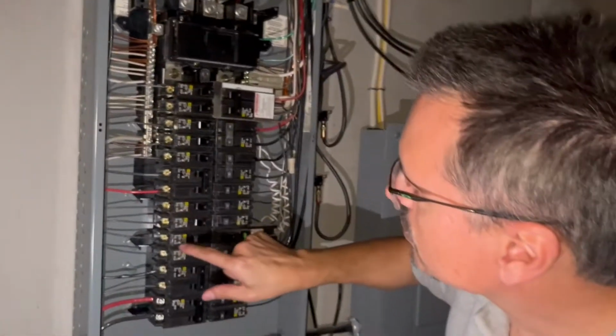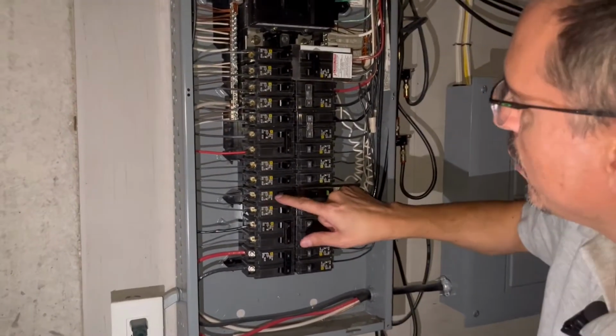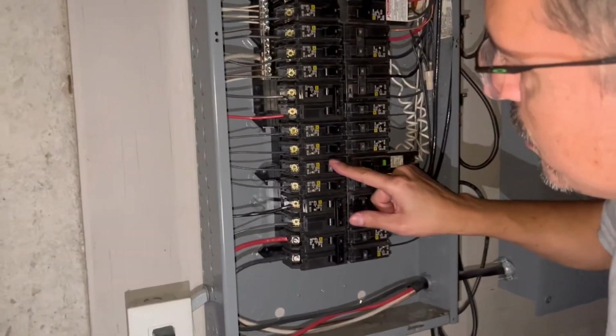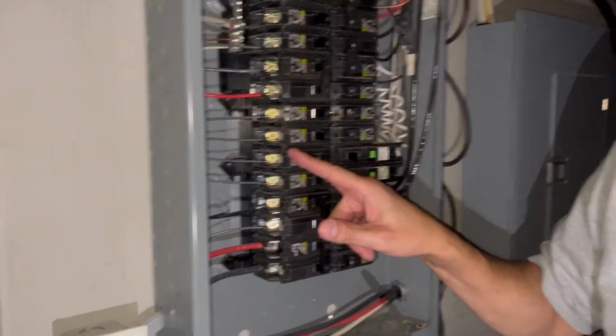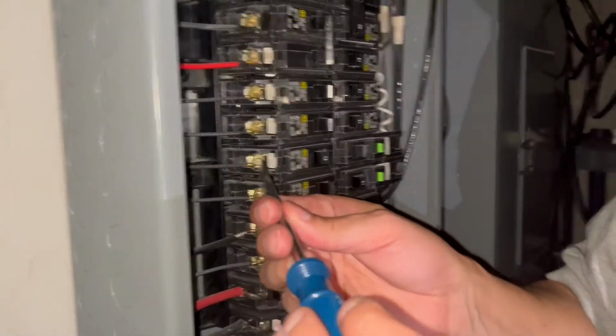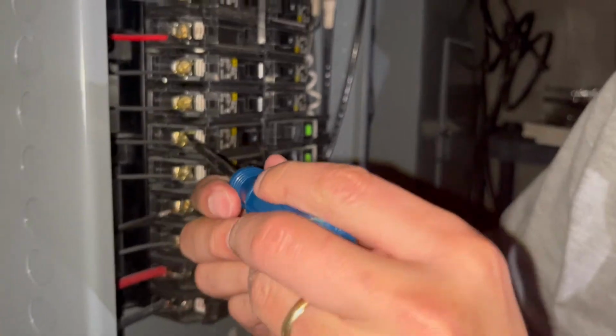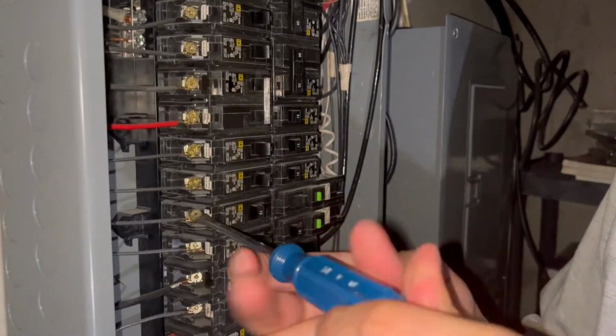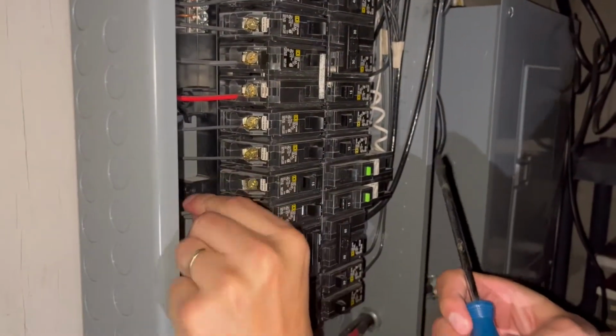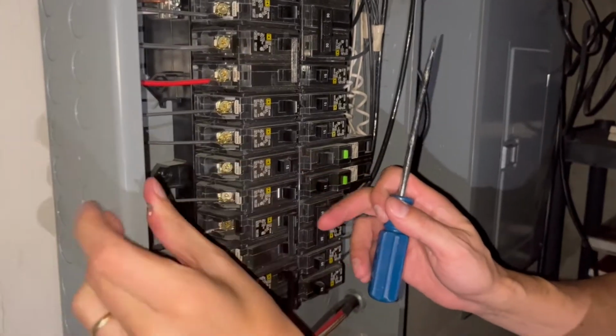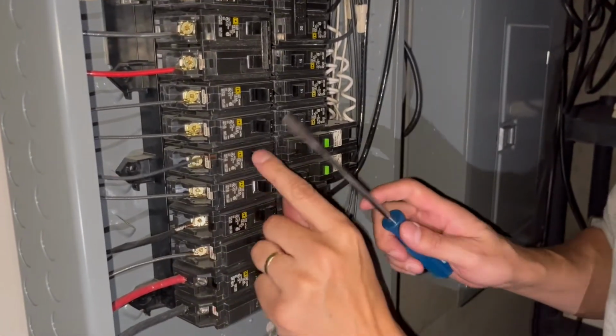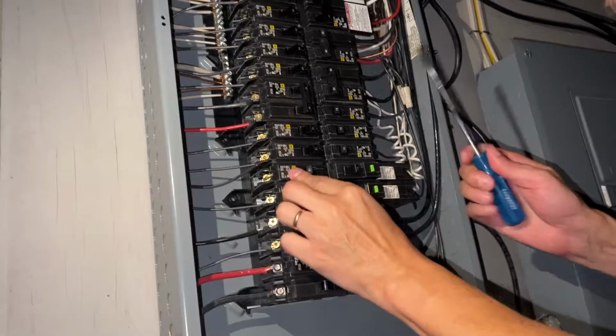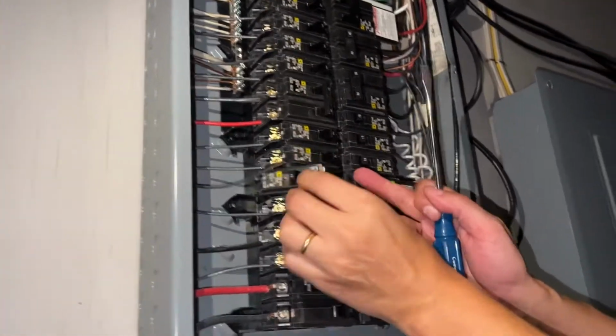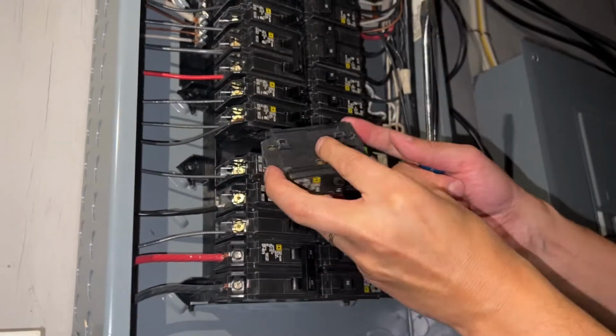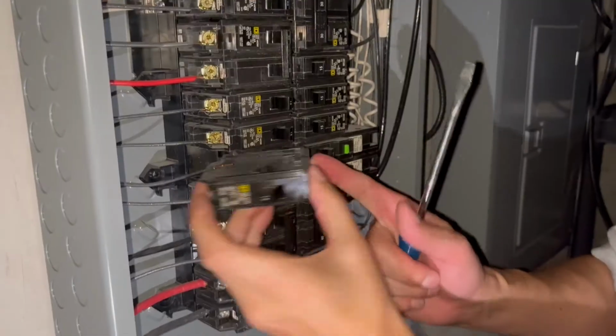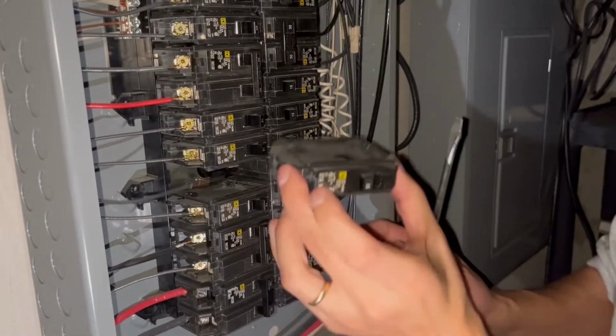Okay, so this was the circuit breaker that we want to replace. With the power off, the first thing we do is remove the wire. You have a screw there and you're simply gonna remove it. You guys can do this yourself. You'll be surprised how easy it is to replace a damaged circuit breaker. Okay, now with that wire out of the way, we can take off our damaged circuit breaker. You're literally just going to rock it out of position and it just pops. So it was secured on this front leading edge and it rolled out almost like a hinge. It'll roll out and pop out.